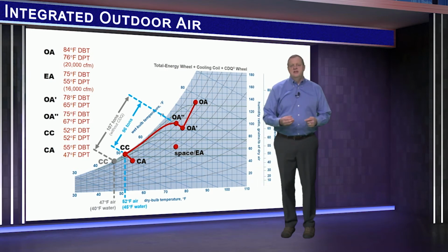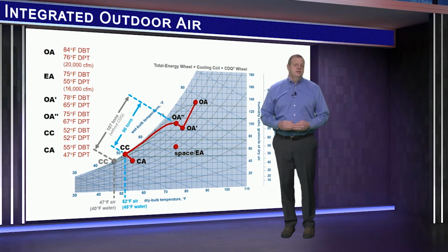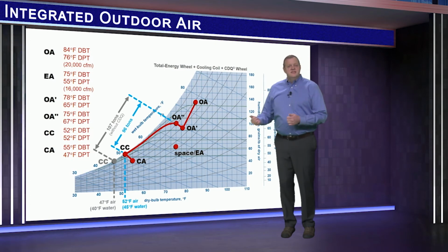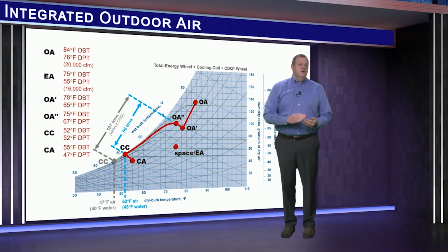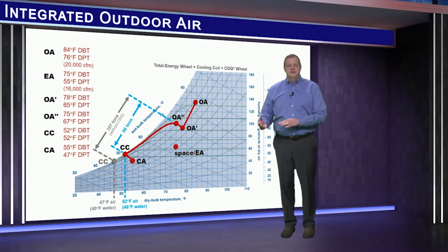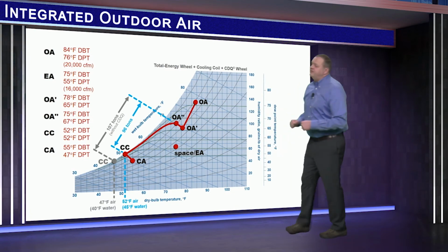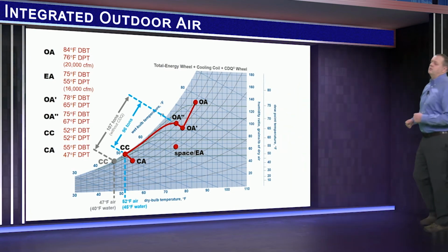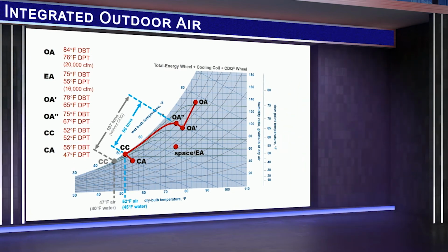Now, as Ryan mentioned, this warmer air offsets less of the zone sensible cooling load, requiring the terminal units to provide more of the sensible cooling capacity. So what happened here is the CDQ wheel shifted 11 tons of load from the dedicated outdoor unit to the sensible coils in the terminal units. That's load shifted from the cold water chiller to the more efficient warm water chiller.